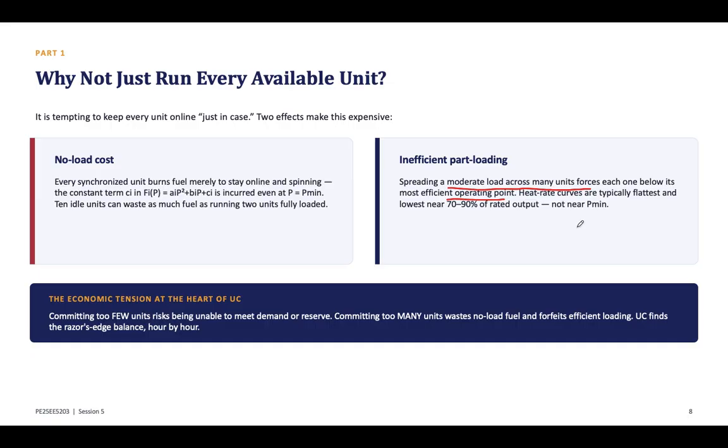Yeah, less committed means if you have 200 capacity and the load is 200, and you're running two generators or three generators, like 60, 60 or 65, 60 something, if there is a sudden inrush of load, you have to start one more generator there, because all of them are already operating at their peak maximum.